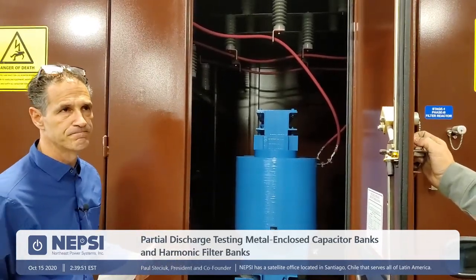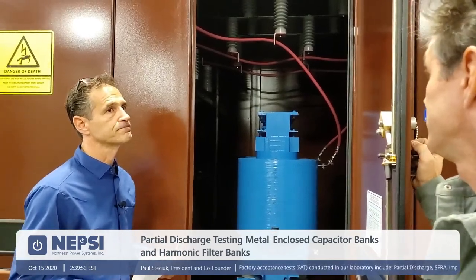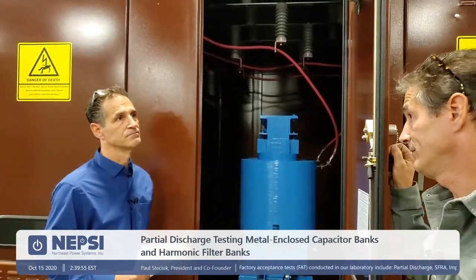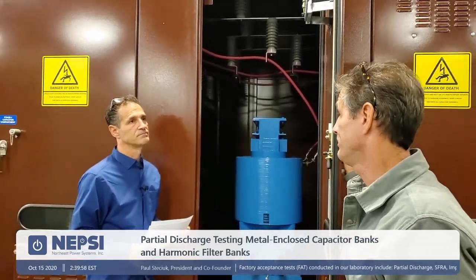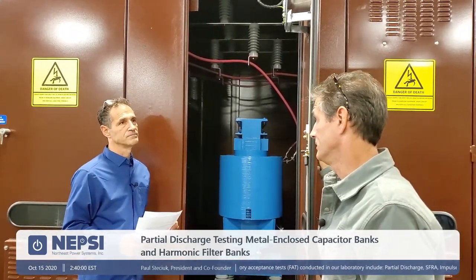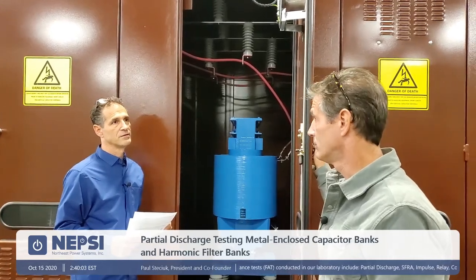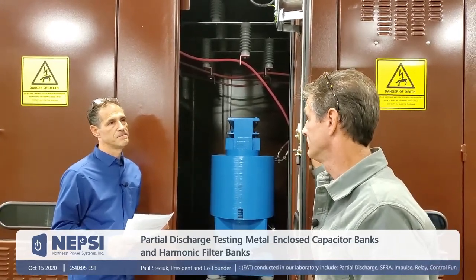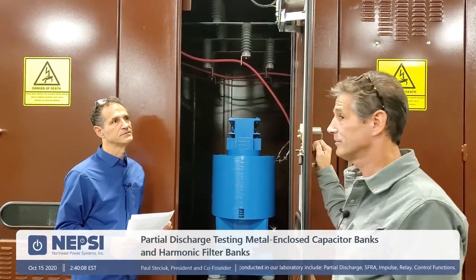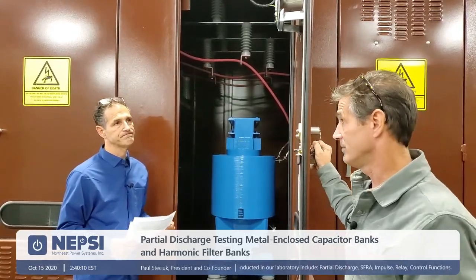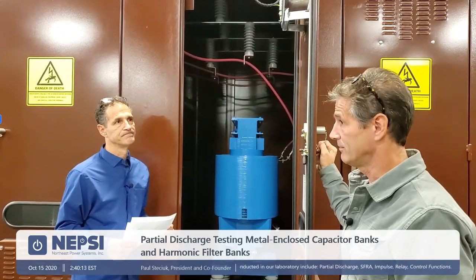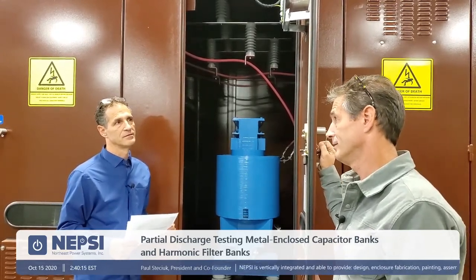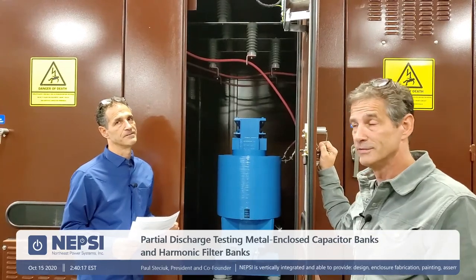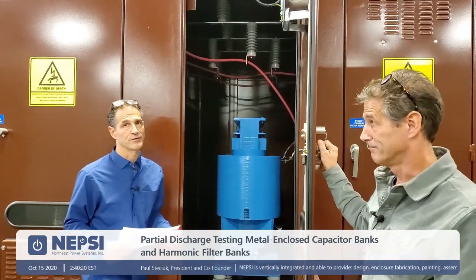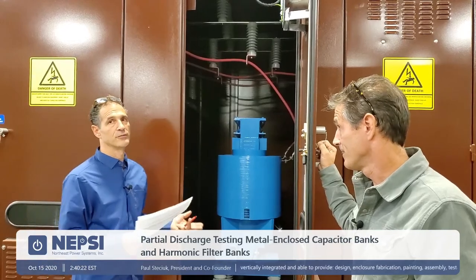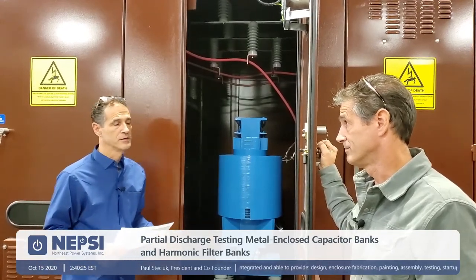Anything else, Pete? Well, the only other thing I wanted to add was this system is built for 200 kV, but for nameplate, it's 170 kV BIL. So we actually have some margin in our design, and that helps us. It makes it look easy for us to pass a test. But maybe if we designed and built for 170, it might have been a more difficult test. Good point. So it's true for impulse testing too. If we design for 200 and we impulse at 170, it's easier to pass.